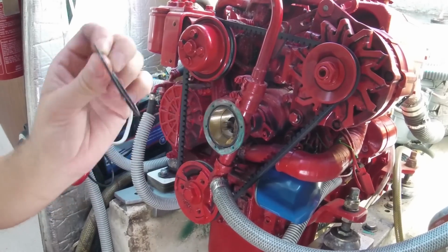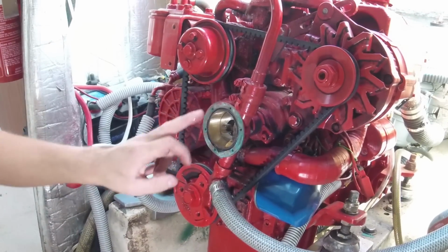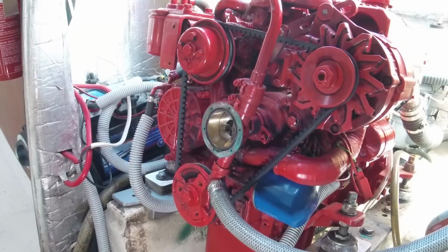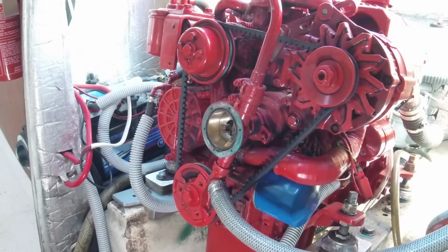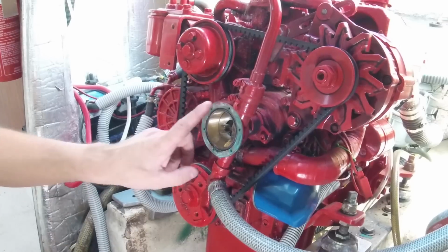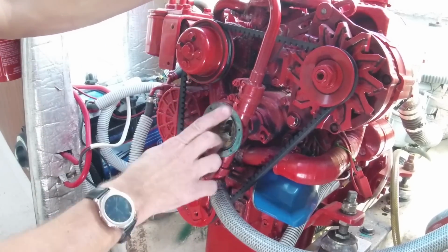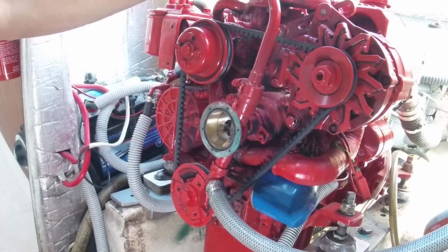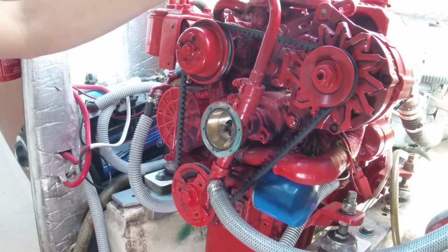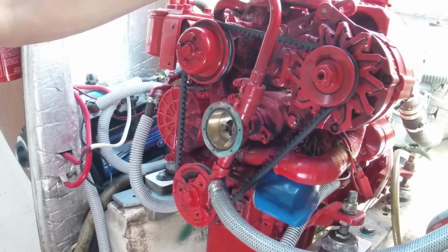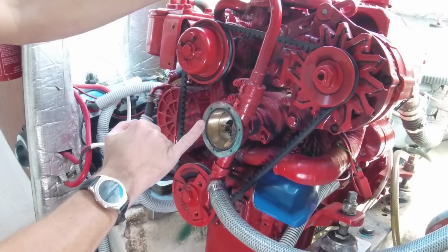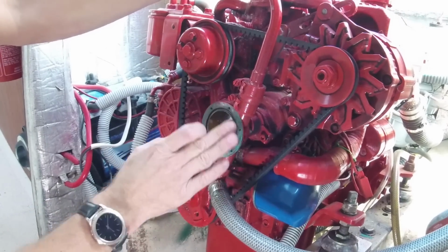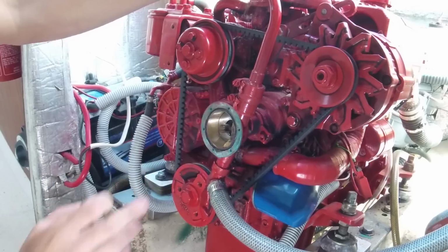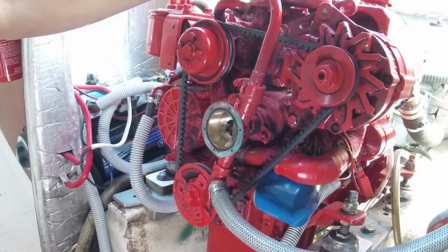But I've bought a kit this time, so I can replace the O-ring. You can buy just the impellers, and as long as you're getting a good seal, you don't need to replace the O-ring. Some older pumps come with a paper gasket, and you'd need to replace that each time. So I've got a bit of verdigris, a bit of corrosion on this face, and I'm going to clean that up before I progress any further.